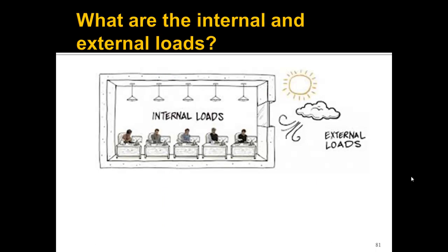Let's think about a building, since that's what we're looking at in utility bill analysis. The external loads include sunlight, wind, and conduction through walls. The internal loads are things like lights, people, computers, projectors — any equipment that uses electricity will also produce heat. The outside temperature at which the internal and external loads balance is called the balance point.